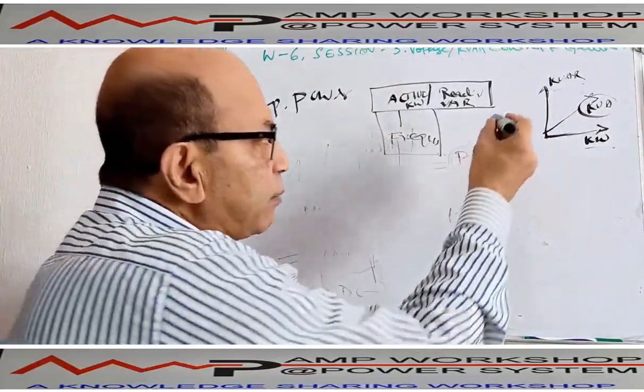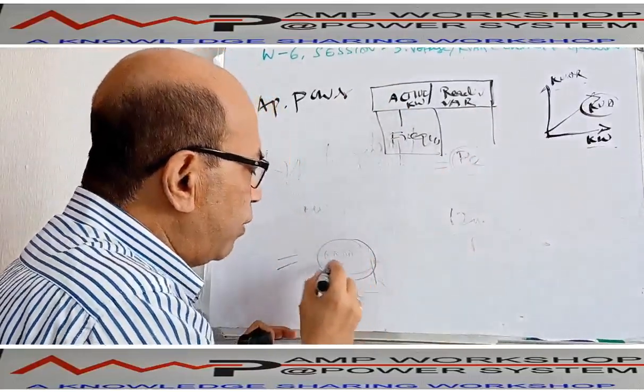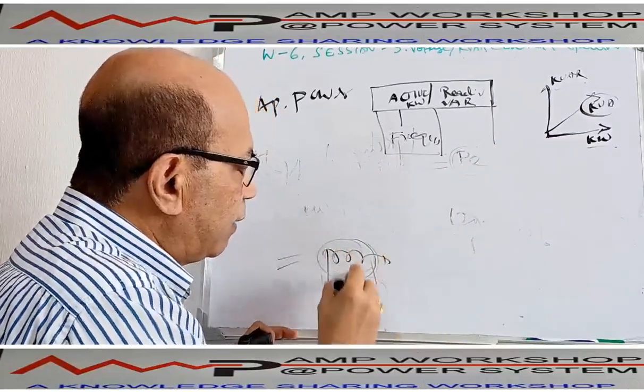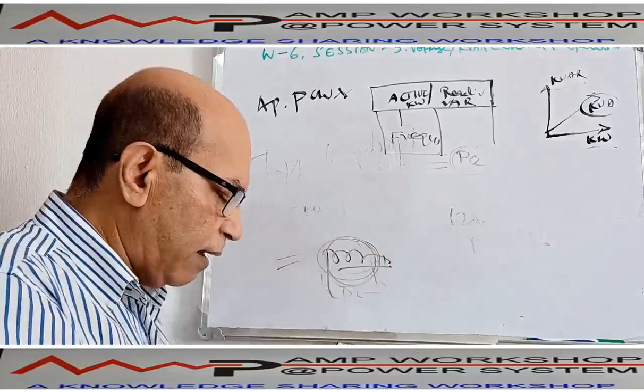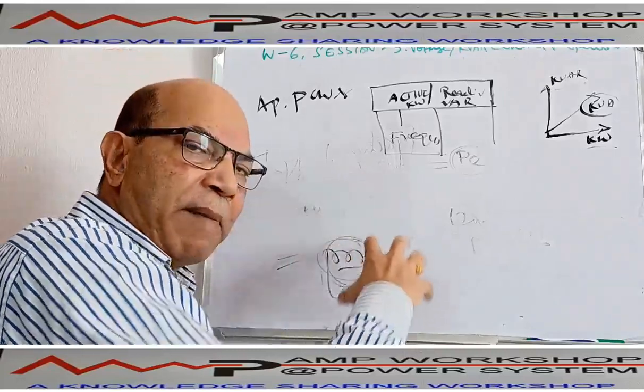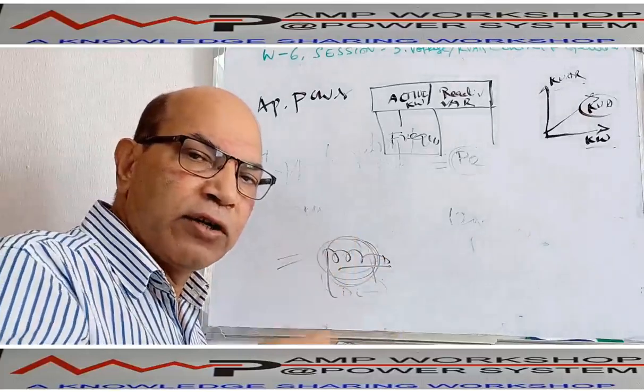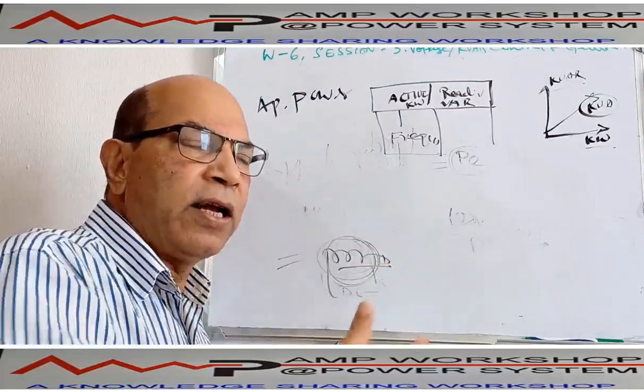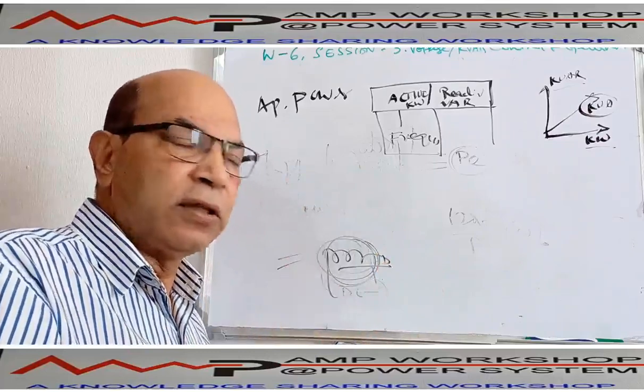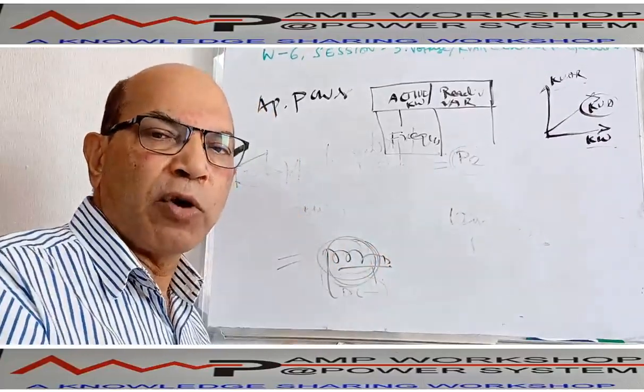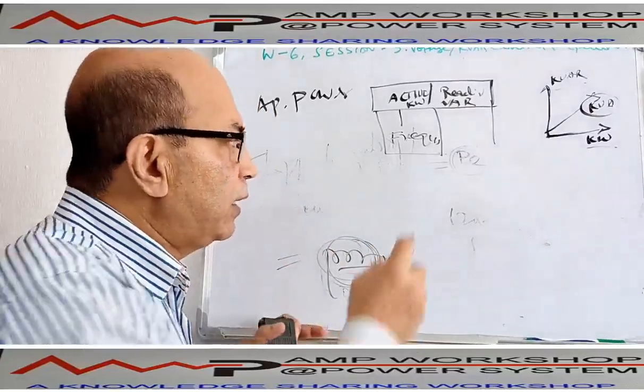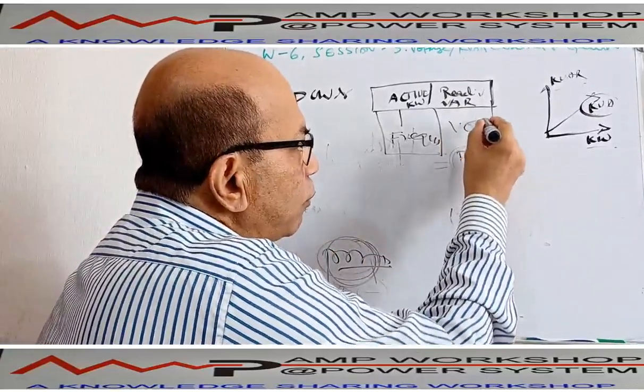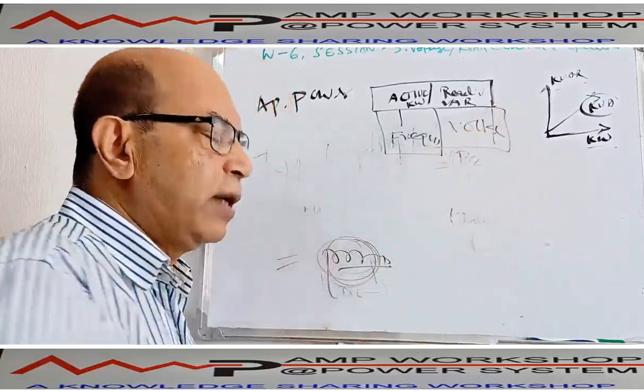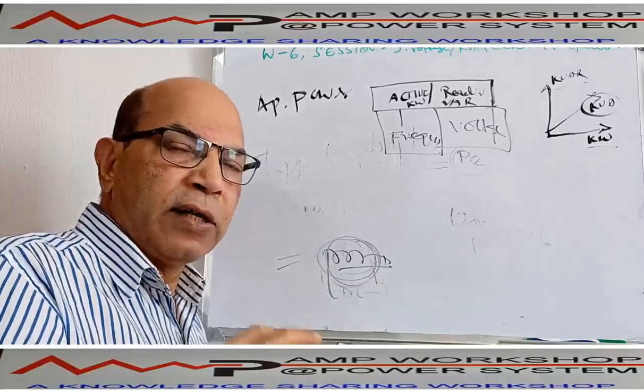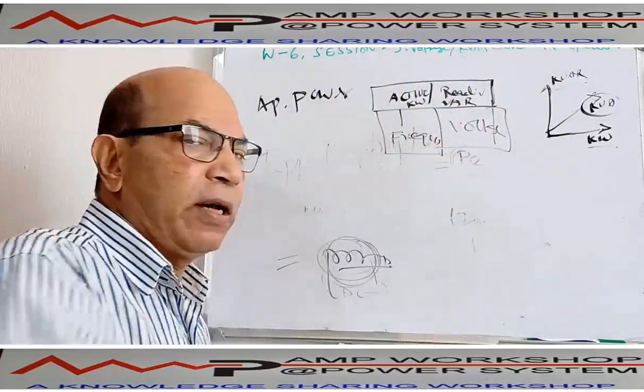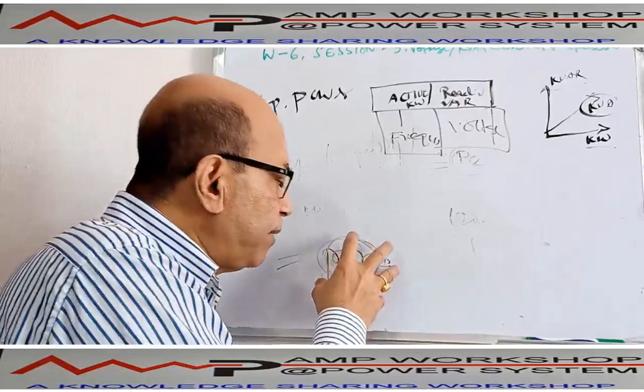Similarly, the reactive power is produced by whom? The exciter. When the rotor coil is getting magnetized, it is producing magnetic flux. When that magnetic flux rotates, it links with the stator winding, and the stator winding produces voltage. So the rotor or excitation system is responsible for the voltage. The excitation system gives you the output voltage, and this output voltage is responsible for the reactive power. That means when you want to get reactive power, you have to produce a voltage, which means you have to give excitation to the rotor.